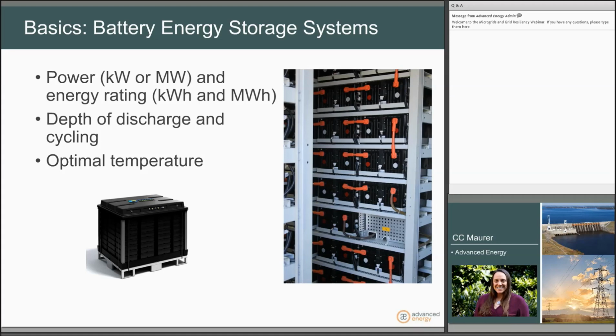Battery systems will have both a power rating in kilowatts or megawatts and an energy rating in kilowatt hours or megawatt hours. Batteries will have different cycling capabilities and depth of discharge. It's important to consider all of these factors in an energy storage system design to compare the technologies. Batteries also have an optimal temperature at which they operate. This means that many batteries need a dedicated conditioning system. In field applications, this has proven to be suboptimally designed for battery performance. The conditioning contributes to the overall auxiliary power requirements for the battery energy storage system and the microgrid in general.